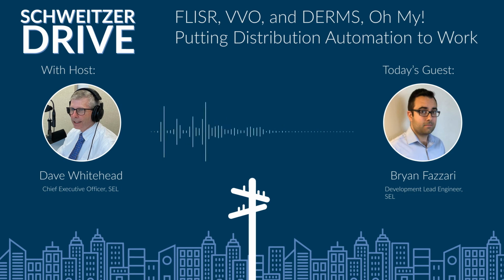Okay, so that brings us back to the third item under distribution automation control, and that's FLISR, fault location, isolation, and service restoration. A lot of that has to do with fault location, and once you know where it is, you know how to isolate the affected part of the power system and restore service to it. Our first relays have been able to calculate fault locations.